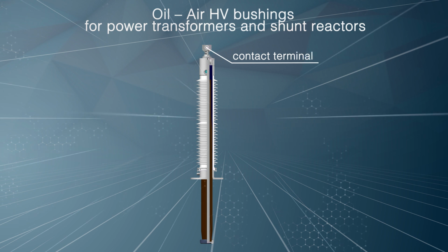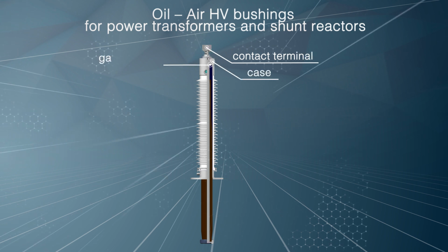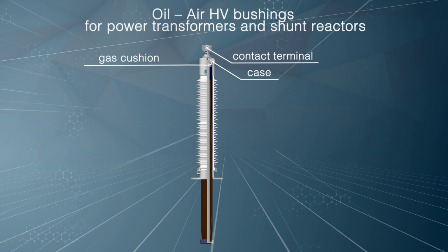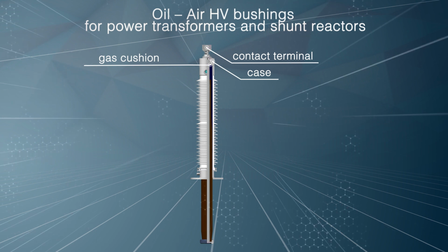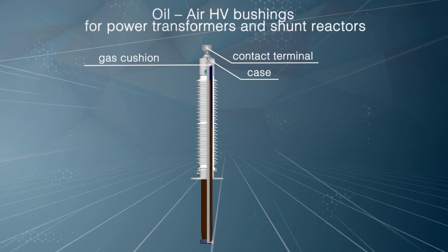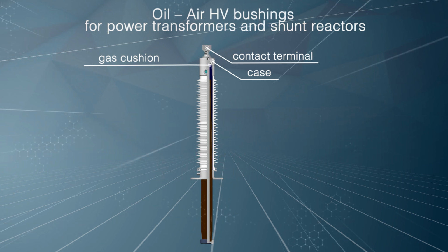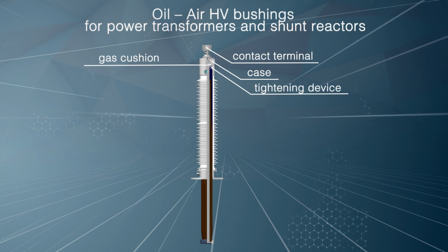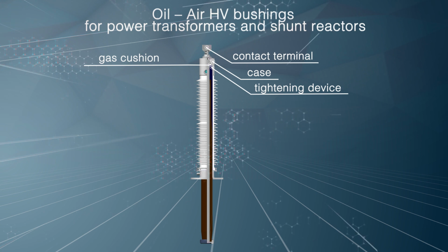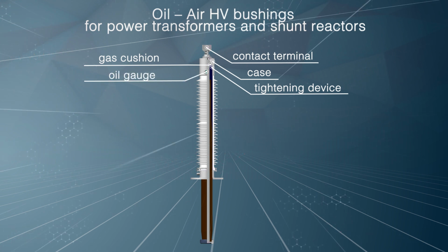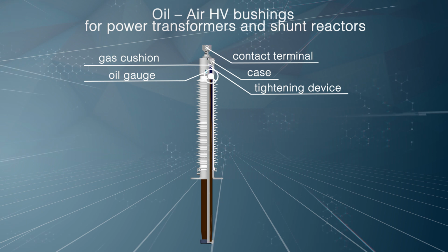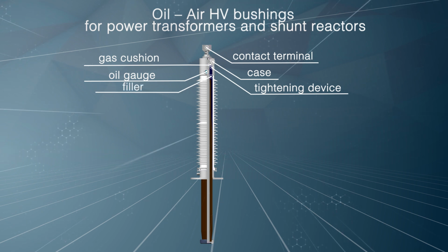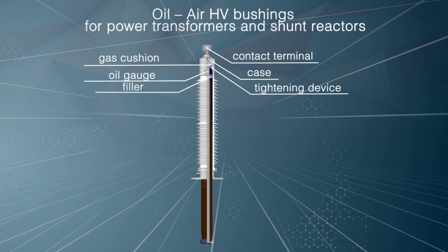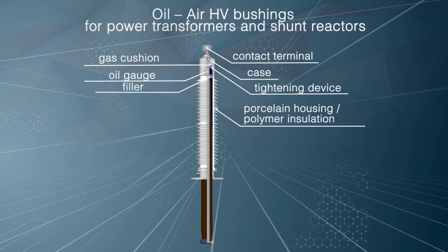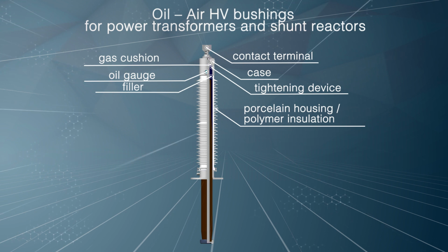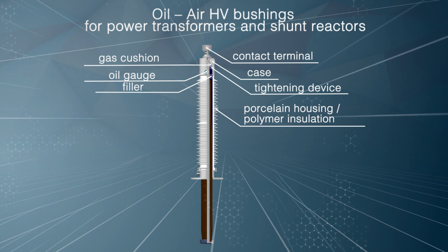Inside the case, these elements of the bushings are placed: gas cushion, some free air or gas to compensate volume fluctuations of the liquid filler caused by temperature changes; tightening device that ensures required mechanical strength and leak tightness of the bushing; oil gauge for control of oil level; liquid filler in the bushing; filler, a dry, gaseous, or liquid substance protecting the bushing's internal space against moistening; porcelain housing, an external insulation of the bushing that protects it from adverse factors of ambient environment and ensures required arcing distance and creepage distance along its outer surface.